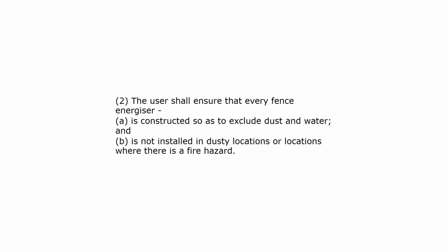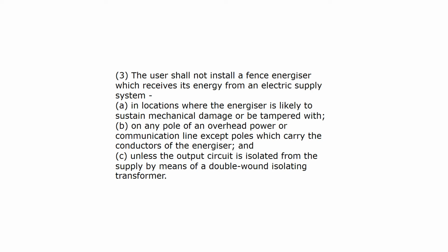The user shall ensure that every fence energizer is constructed so as to exclude dust and water and is not installed in dusty locations or locations where there is a fire hazard. The user shall not install a fence energizer which receives its energy from an electric supply system (a) in locations where the energizer is likely to sustain mechanical damage or be tampered with, (b) on any pole of an overhead power or communication line except poles which carry the conductors of the energizer, and (c) unless the output circuit is isolated from the supply by means of a double wound isolating transformer.